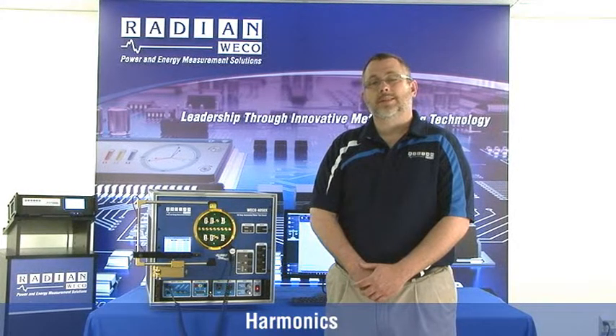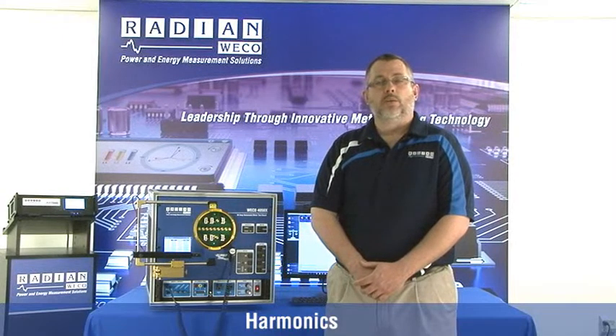You may be thinking this is great information. Where can I find these nonlinear loads so I can observe this phenomenon for myself? The fact is, nonlinear loads are everywhere. A few examples of nonlinear loads include variable speed drives, rectifiers, computer power supplies, fluorescent and LED lighting, and a host of other common electronic loads. The modern world is full of nonlinear loads.